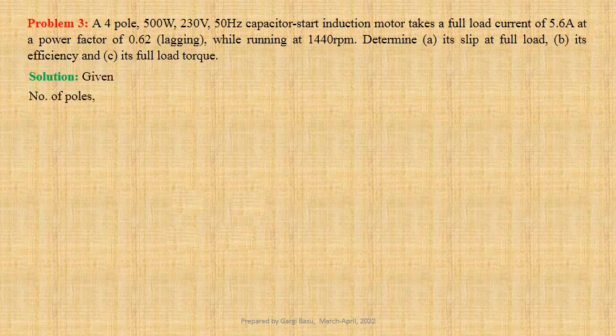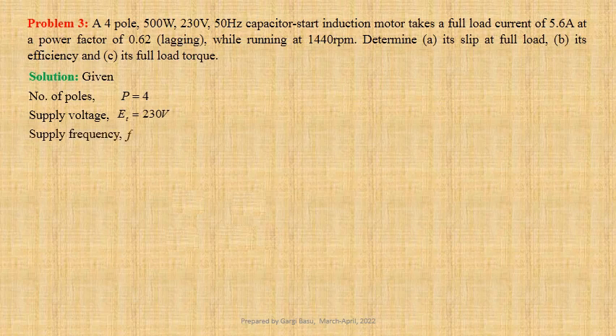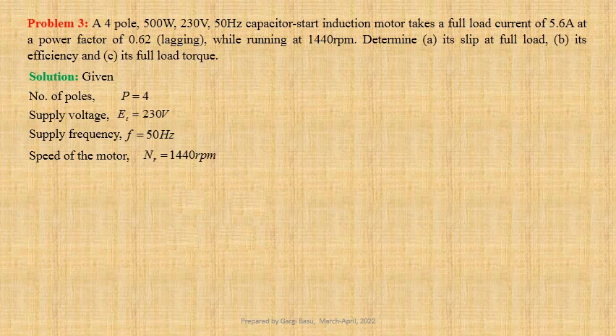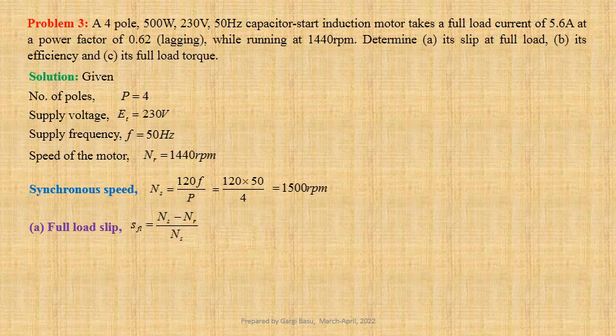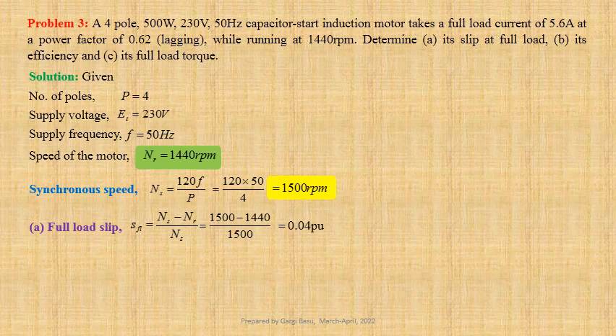Number of poles of the machine P equals to 4. Supply voltage Et equals to 230 volts. Supply frequency F equals to 50 hertz. Speed of the motor Nr equals to 1440 revolutions per minute. Let us now calculate synchronous speed. Ns equals to 120F by P. Using values we get 120 into 50 divided by 4, that gives us 1500 revolutions per minute. Full load slip SFL equals to Ns minus Nr divided by Ns. Using values we get 1500 minus 1440 divided by 1500, that gives us 0.04 per unit or 4%.